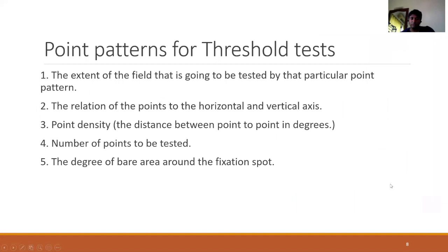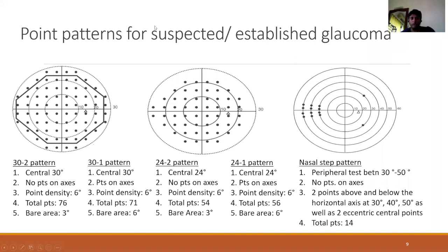Point patterns are divided into multiple types based on five criteria: the extent of field tested, the relation of the points to the horizontal and vertical axis, the point density (distance between two consecutive points in degrees), the total number of points to be tested, and the bare area around fixation where there will be no points. Point patterns used for glaucoma suspects or early established glaucoma are mainly the 30-2, the 24-2, and the nasal step. The most commonly used are the 30-2 and the 24-2.